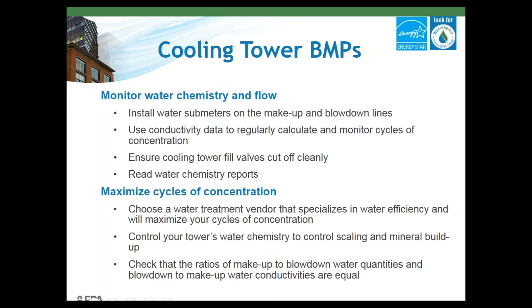When maximizing your cycles of concentration, you should work with a water treatment vendor that shares your goal to achieve water efficiency. Working together, establishing target cycles of concentration based on your local water chemistry and water treatment plan will help keep your cooling tower operating in a good place and also keep your water bill down. Also, with your makeup and blowdown water meters, evaluate the ratio of makeup to blowdown quantity as a double check on your cycles of concentration, just a quick back of the envelope calculation. And typically, your treatment vendor will leave behind or send you a written report of the status of your cooling tower chemistry each time they visit to check your system. This is often done on a monthly basis, and review the reports to make sure your cycles of concentration are being maintained. Next slide, please.